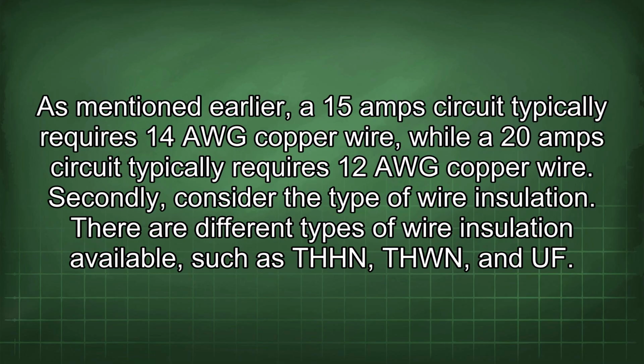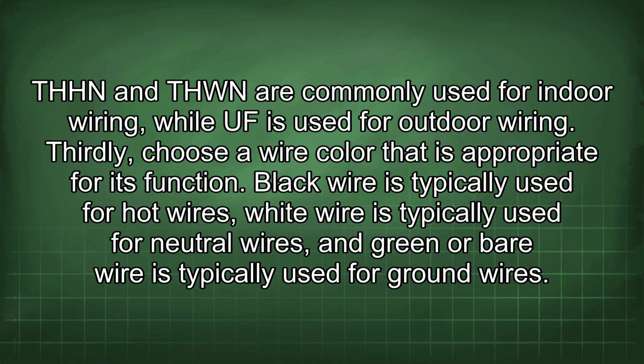As mentioned earlier, a 15 amp circuit typically requires 14 AWG copper wire, while a 20 amp circuit typically requires 12 AWG copper wire. Secondly, consider the type of wire insulation. There are different types of wire insulation available, such as THHN, THWN, and UF. THHN and THWN are commonly used for indoor wiring, while UF is used for outdoor wiring.